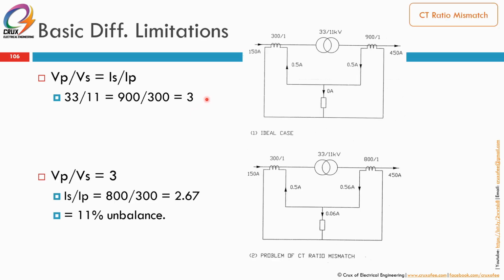Okay, first problem, CT ratio mismatch. How is this a problem? Let's see an ideal case. We use CT primary 300/1, secondary 900/1, and the transformer is 33/11. The ratio of primary to secondary winding turns is the same as for the CTs, so 33/11 equals 900 over 300, which gives 3. Say there's a current of 150 amps flowing through here. On this side it converts to 450 amps. On the secondary, it will read 0.5 on both sides. So when IDIF reads, IDIF is 0.5 minus 0.5, giving 0 amp.